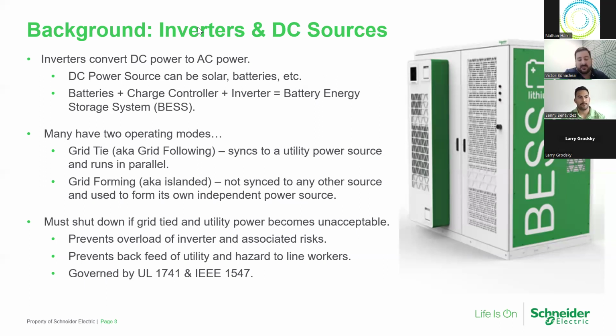In common applications, that's the utility power source tied into the inverter. The inverter synchronizes to that utility source and provides power out in parallel with it to help subsidize your energy costs, for example. The other operating mode is grid forming mode, or islanded mode, which means there is no other source on the system. The primary source is the inverter itself, without synchronizing to any other anchor resource. It provides power onto a bus for the loads to consume without syncing up to anybody else. It's running independently, basically.